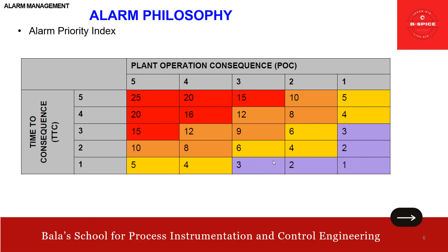Whatever the communication loss, the designer of the control system has built in high redundancy, so most control system alarms will not have an immediate consequence. So POC 2 only. Then what is this TTC? Control system alarms are not considered the responsibility of the operator, because it's a communication issue. Their interpretation requires dedicated expertise, so the operator simply needs to inform the automation team to undertake the necessary action. So POC 2 and TTC 1. That means again the priority index is 2.